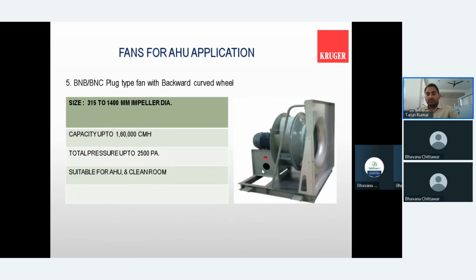Then further to that, the plug fan, which is very well known in the ventilation segment for the air handling unit. This again has a backward curve, and it comes direct driven, which reduces the belt losses, because when you go for the centrifugal fan, they are basically used with a belt driven unit. Whereas the plug fan is used direct driven, there is no belt loss, so it has better efficiency than the centrifugal fan.